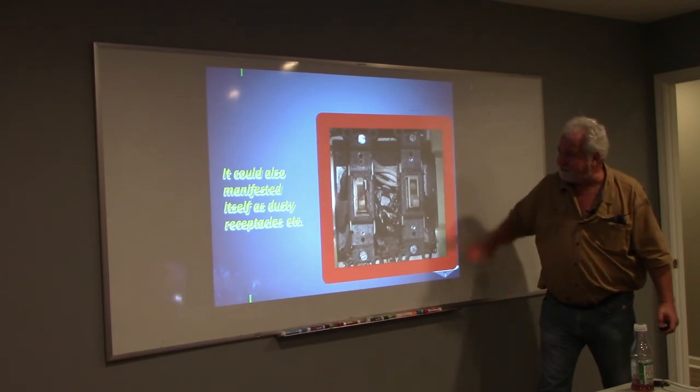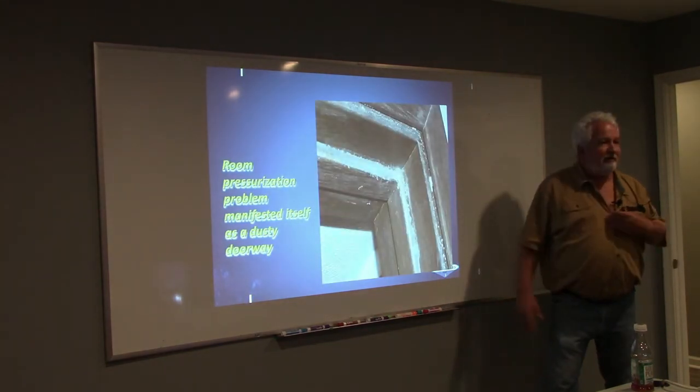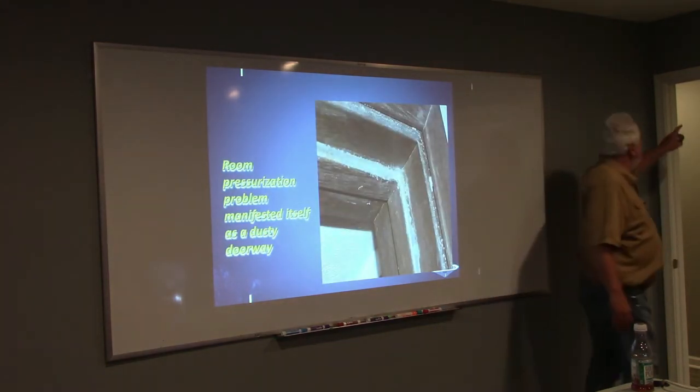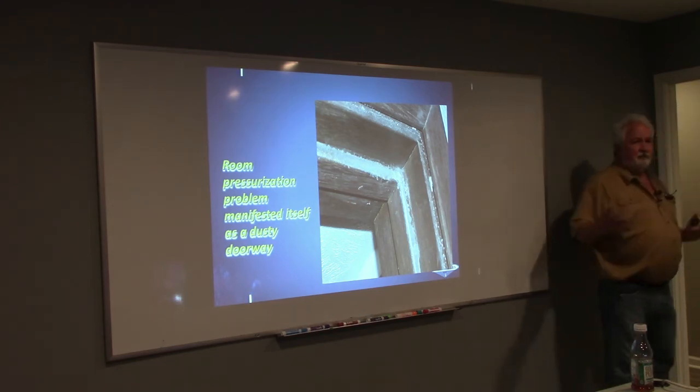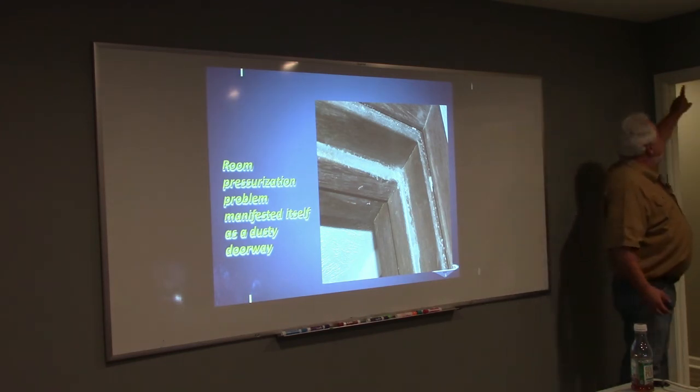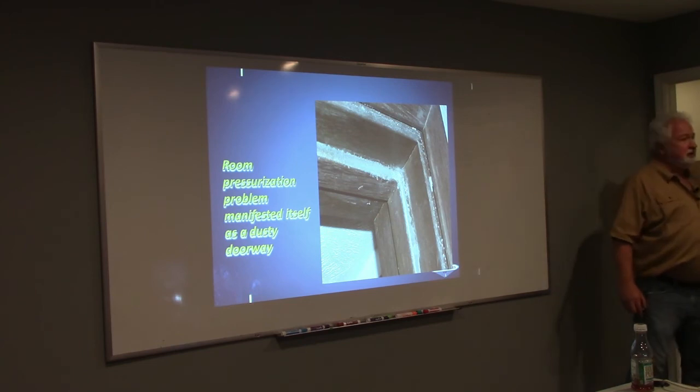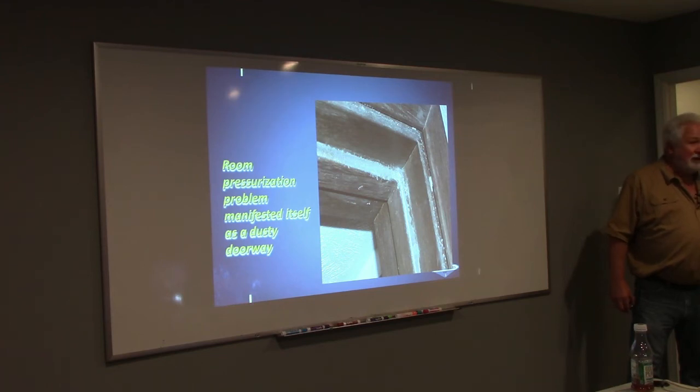Oh, my favorite, the door jamb. I never closed that door. Well, if I'm seeing dust in a door jamb, that means that door must have been closed, because now the air is going around it, so my door frame is becoming my filter.